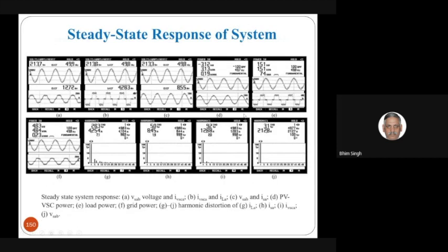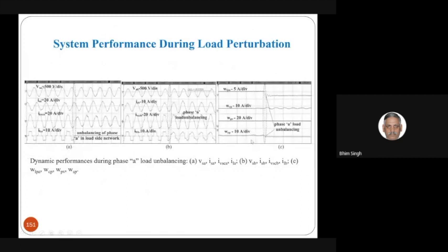So these are typically the performance under the fault, and these are of course the distribution result of grid current, and this is, you can call it, load current, and this is the inverter current. You can say the THD of the load current is 26.3%, but the grid current here is only 5%, where the voltage THD was also 3.1%, and the inverter current THD is typically 9.2%.